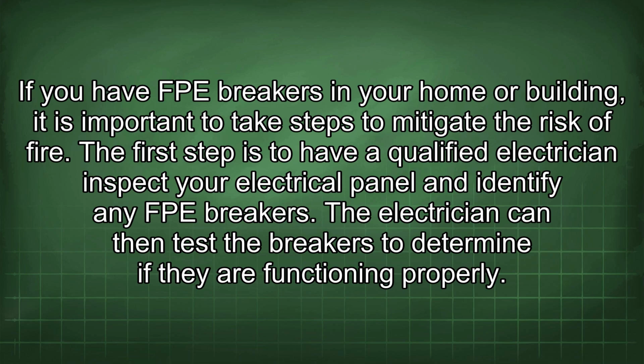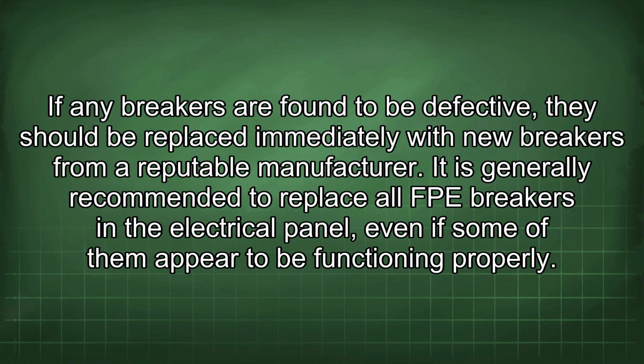The first step is to have a qualified electrician inspect your electrical panel and identify any FPE breakers. The electrician can then test the breakers to determine if they are functioning properly. If any breakers are found to be defective, they should be replaced immediately with new breakers from a reputable manufacturer.